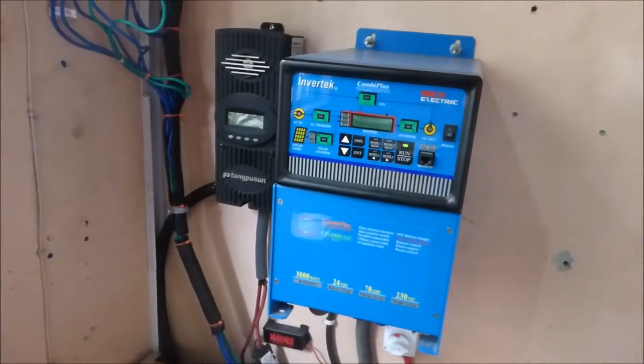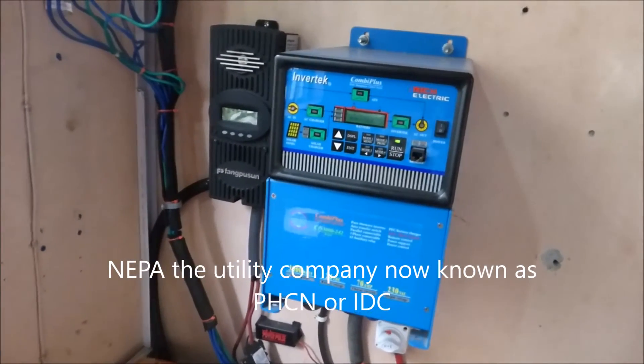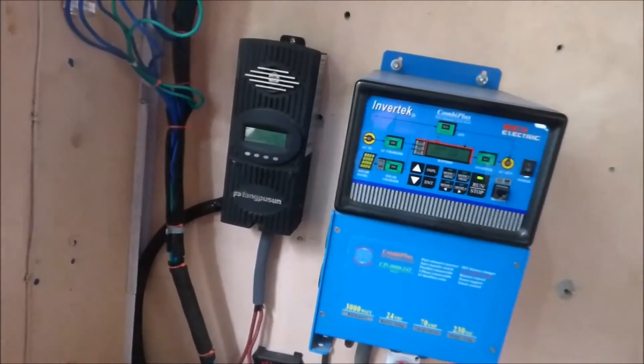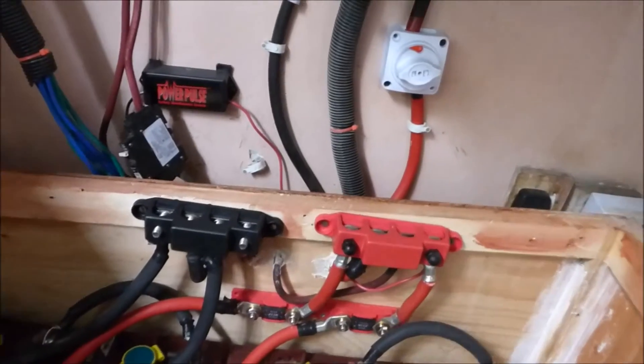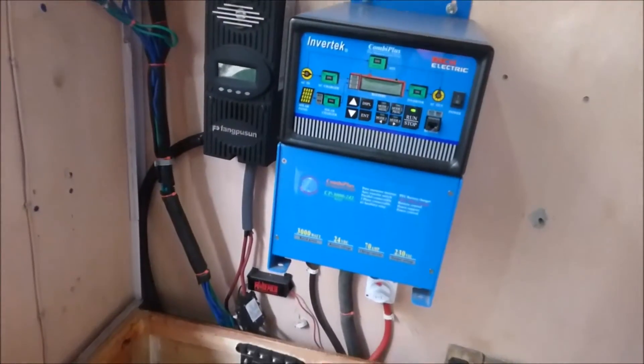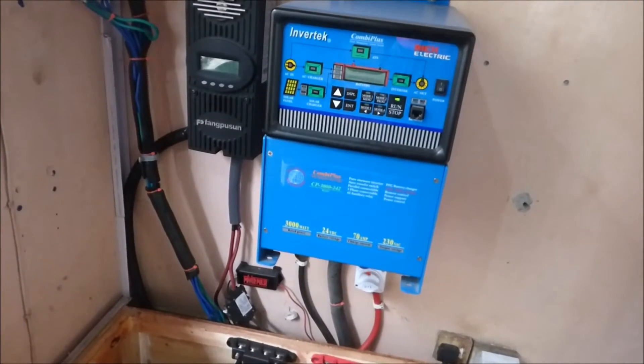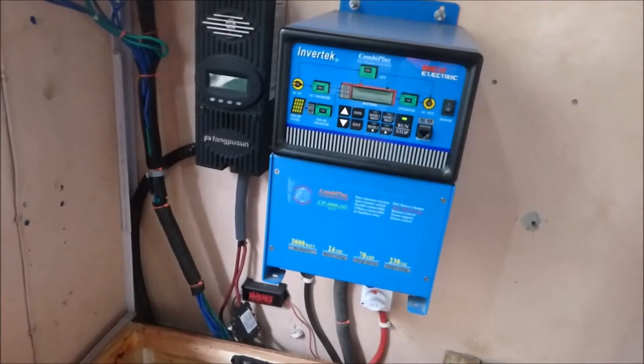Because we were not able to properly charge them and NEPA has been absent for quite a while, we had batteries that consistently gave us problems. You'd have batteries where one cell gives 6 volts, another 6 volts, another 6 volts, and one only 4 volts — and that was repeating itself over and over again. The only way to correct that is by properly charging these batteries, getting them to 29 or 30 volts, and being able to equalize them — a deliberate overcharge for 2 hours at 32.4 volts. A 1 kilowatt panel system couldn't do it.